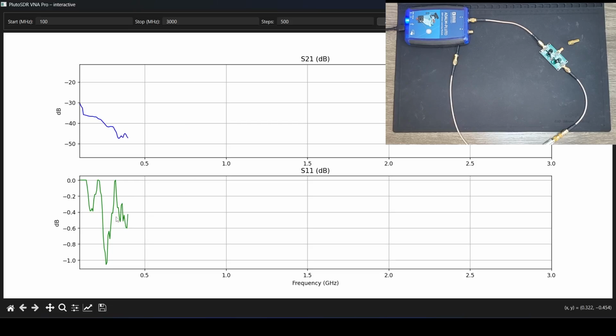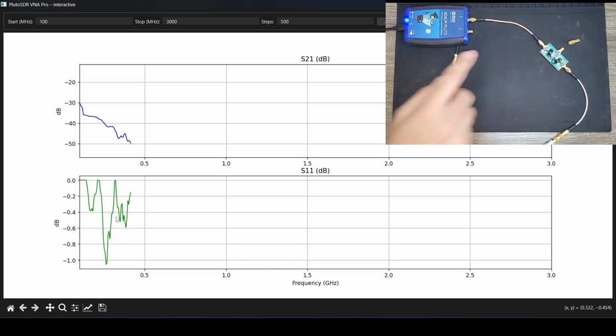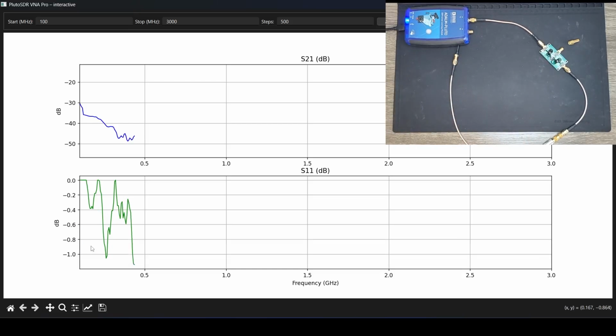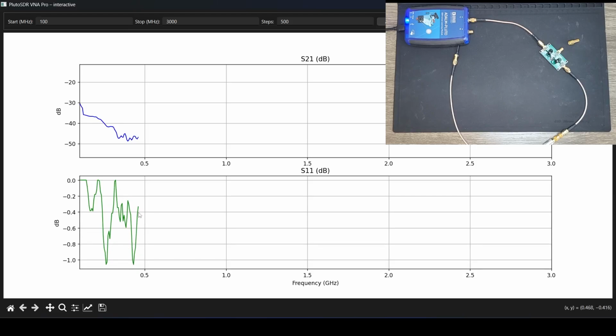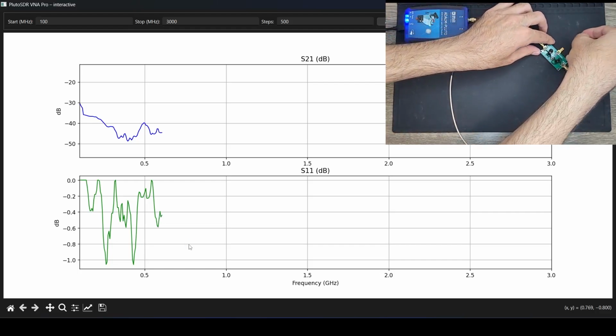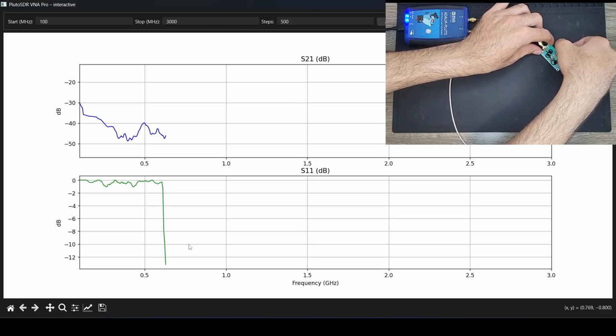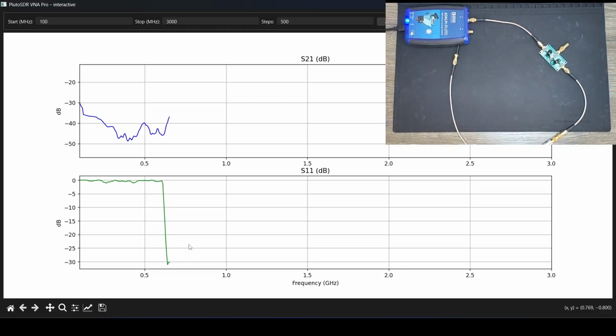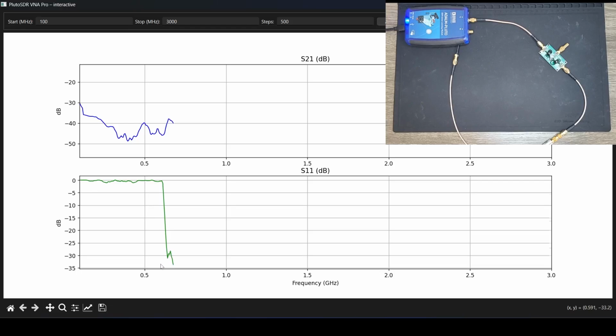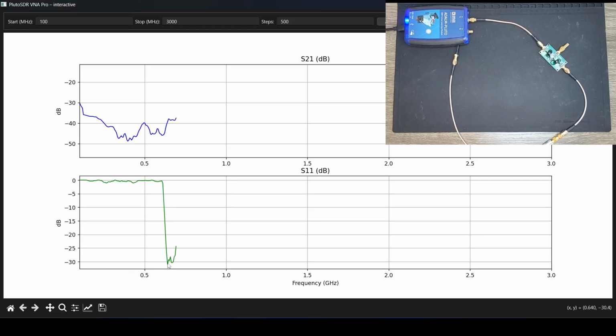And you can see now that the DUT is open, nothing is connected here. The S11 that we are measuring is around -1 to 0 dB after the calibration data is applied. Please ignore the S21 for now because I have not connected the S21 to the first RX channel, because for this video we just focused on S11, how the calibration works and how it behaves. Now what I'm going to do is connect the 50 ohm termination load back to the DUT. You can see as soon as I connect the load, S11 drops to -30 dB.